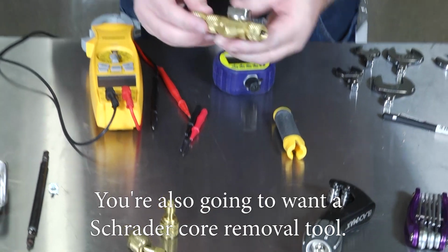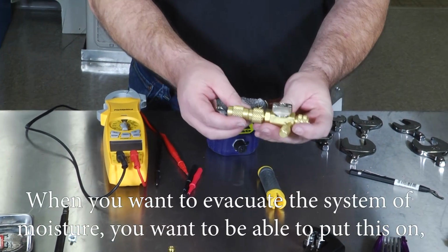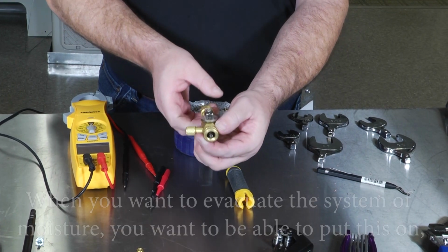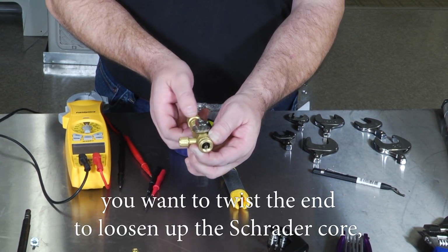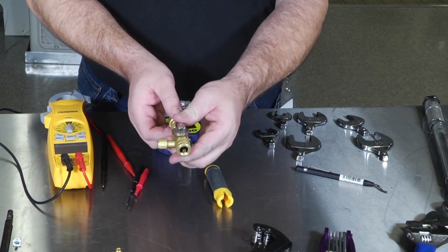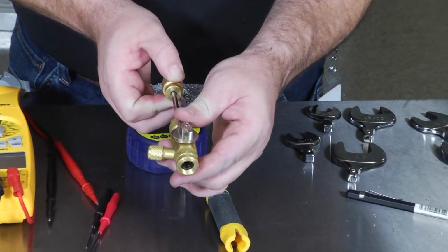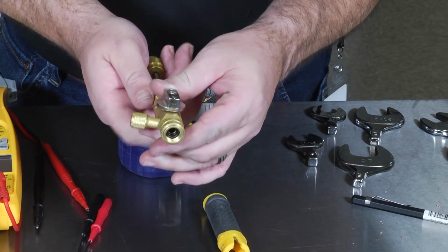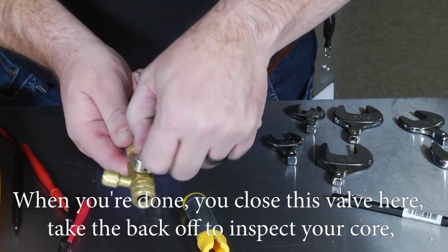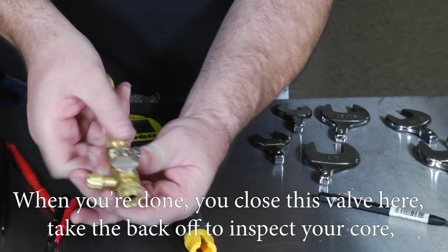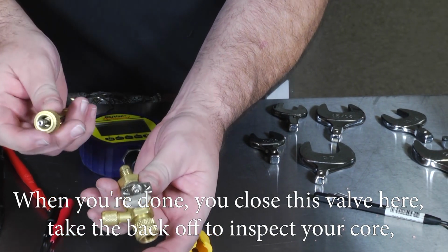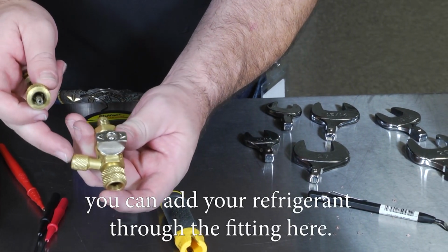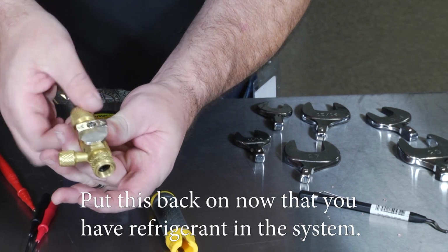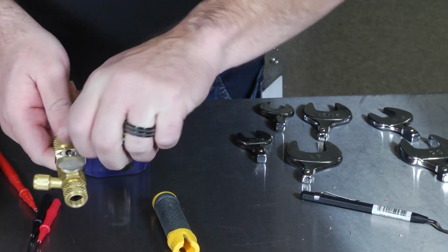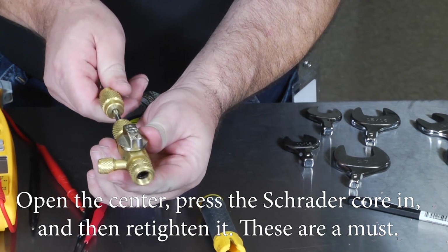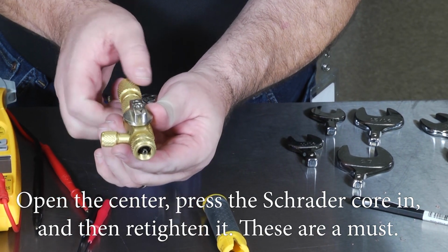You're also going to want a Schrader core removal tool. When you want to evacuate the system of moisture, you want to be able to put this on. You want to twist the end to loosen up the Schrader core and pull it back to completely remove the Schrader core. This will speed up the evacuation and charging process. When you're done, you can close this valve here, take the back off to inspect your core. You can add your refrigerant through the fitting here. Put this back on now that you have refrigerant in the system. Open the center, press the Schrader core in, and then retighten it.